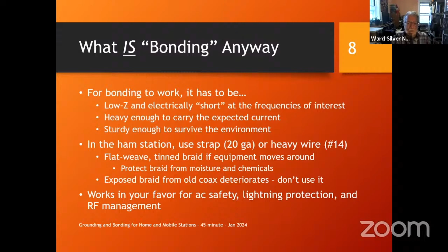When you do this bonding, using proper conductors and keeping runs short and direct as much as possible, this works in your favor. It creates a perfectly good grounding and bonding system for AC safety, lightning protection, and RF management.